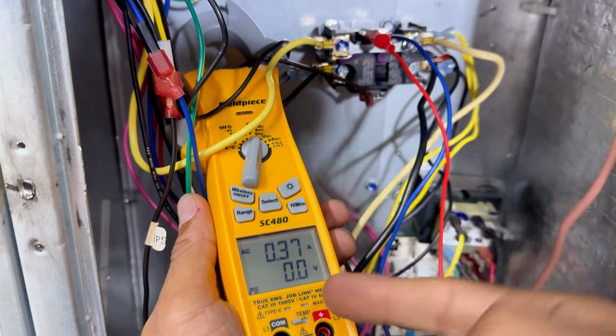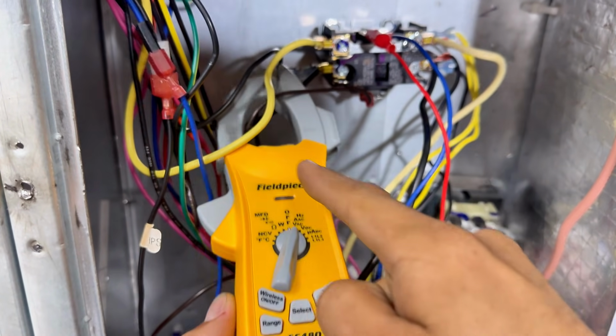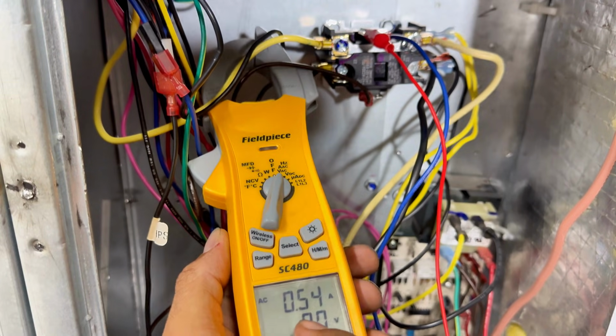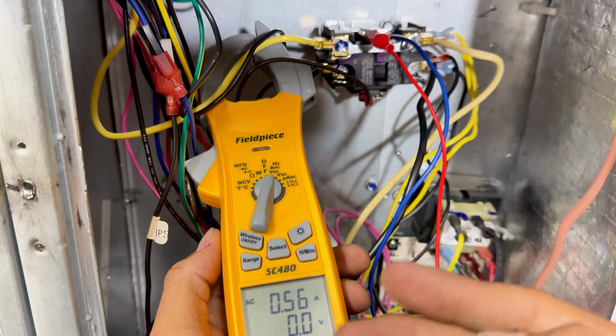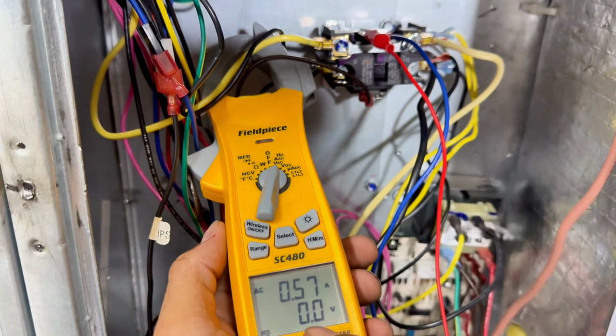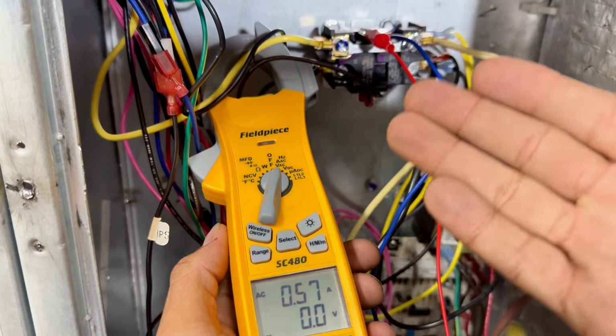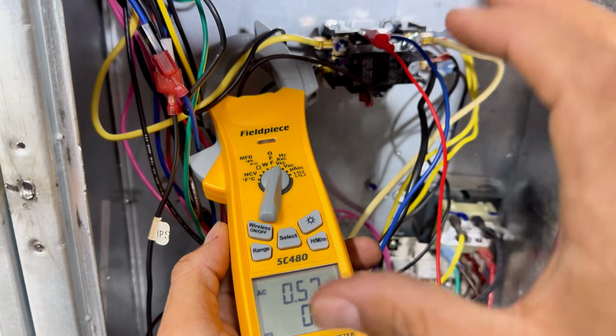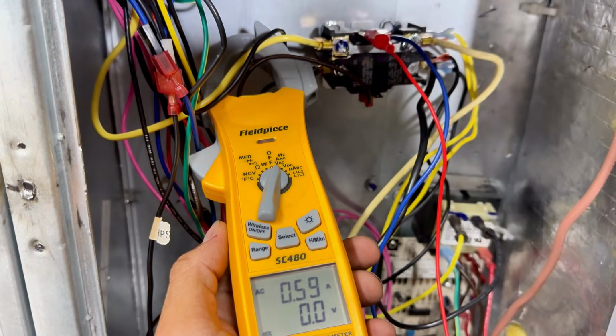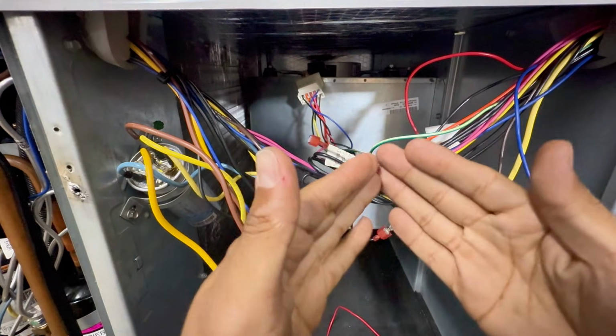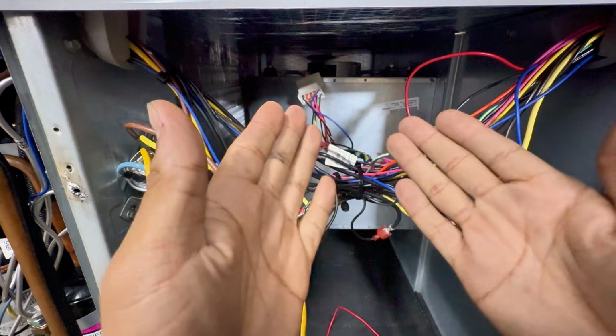I'm checking my current on one wire, brown. On this one, on the common. But look, now it's 0.5, so that's how much current it's pulling right now. But you see, you can check and confirm that it is pulling current even on a low voltage component like the contactor coil. Okay, so now we're gonna check the indoor motor, the ECM.